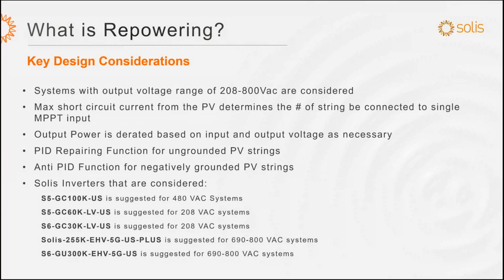The other part is the PV side. Because of the older modules, in most cases we would need to parallel multiple strings in a single MPPT, and that's where we evaluate the short circuit current rating of the current PV modules to make sure they could be combined and connected to the single MPPT inputs of our inverters. Then, based on the output voltage and input voltage rating required, we will derate the output power of the inverter to make sure the inverter is operating in a safe operating area and we meet the requirements of the site.